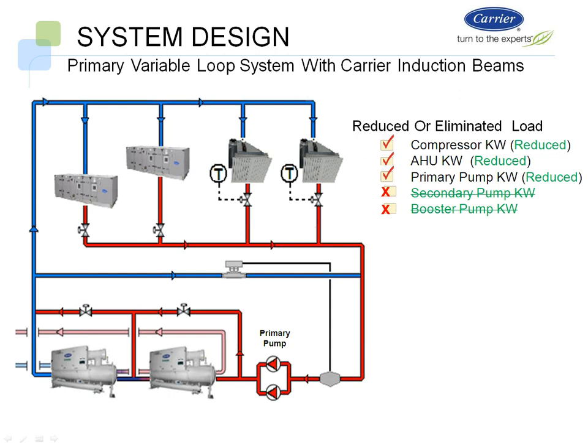So the cost of that. I'm sorry, Mark. So the cost of that air handler should be for that dedicated outdoor air system, where maybe in the past they wanted to use some sort of Munters type unit where we're getting the grains of moisture down to a certain level in order to handle a case where the wet bulb temperature is raised. Now we can use a standard air handler, and it's a little cheaper. Is that correct?